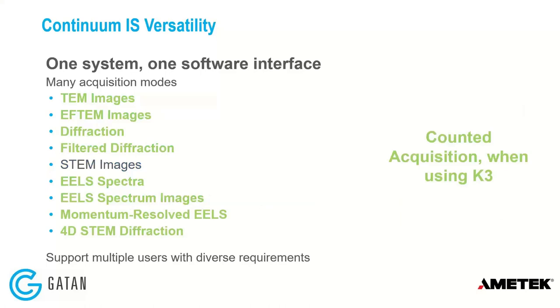A number of these capabilities, these different acquisition modes, can now be done in counted acquisition mode if you're using the K3. The only one that doesn't apply to is STEM, since we're using a STEM detector and not a camera. But for all of these other techniques, these can be counted using a counted acquisition mode if you have the K3 option for the Continuum. That's one I highly recommend — it really decreases the amount of noise in your data and gives you the very best results when you're operating the K3 in counted mode.